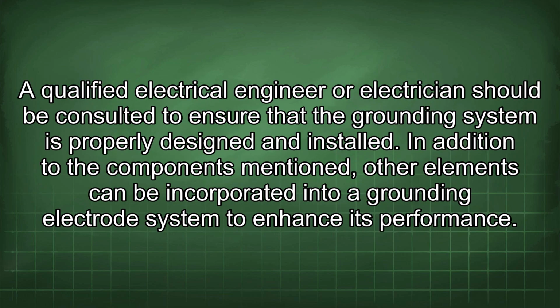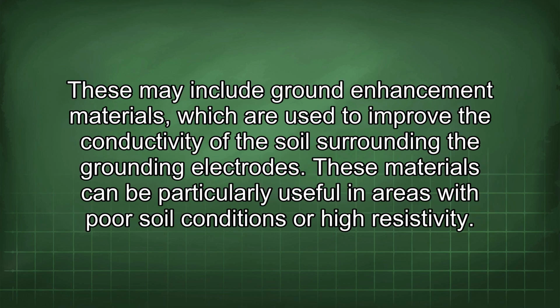A qualified electrical engineer or electrician should be consulted to ensure that the grounding system is properly designed and installed. In addition to the components mentioned, other elements can be incorporated into a grounding electrode system to enhance its performance. These may include ground enhancement materials, which are used to improve the conductivity of the soil surrounding the grounding electrodes. These materials can be particularly useful in areas with poor soil conditions or high resistivity.